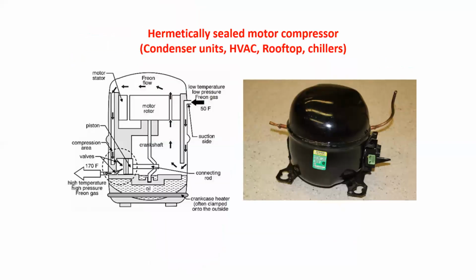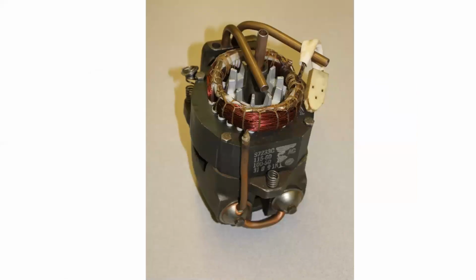We have hermetically sealed motor compressors, which are a unique type of motor that is mechanically and permanently connected to the compressor that is used to compress the refrigerant in the HVAC system. The motor and compressor assembly are then sealed inside a capsule and welded shut, so there's no real maintainable items in it. If something goes wrong, the entire object is then removed and replaced in the system. This is what the motor looks like inside the capsule.